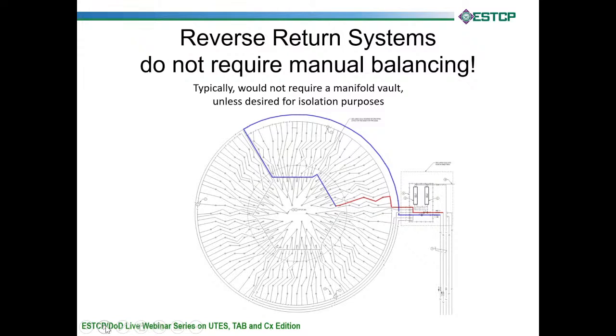So let's start off with reverse return systems. What are they? How do they work? And how do you balance them? Well, a reverse return system actually doesn't require any balancing of these circuits. We'll call them sub-circuits. And they wouldn't require a manifold vault to house all the balancing valves. If you had a traditional geothermal heat exchanger, you would need a vault. You need somewhere for all the balancing valves to be. Well, if you design your system with a reverse return, you don't need the vault, unless you just want the vault for isolation purposes. Then by all means, there's nothing wrong with the vault.